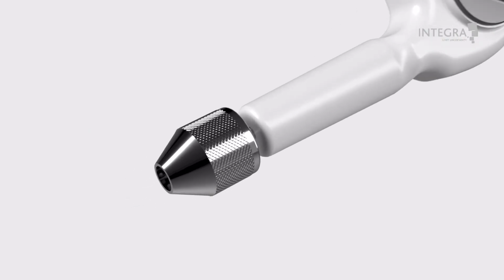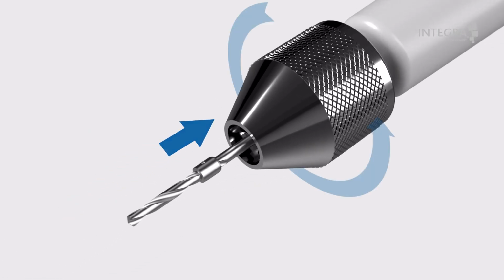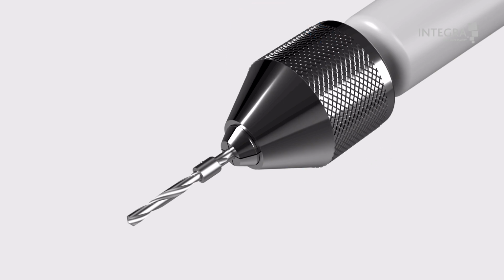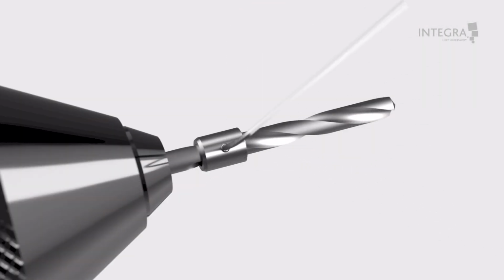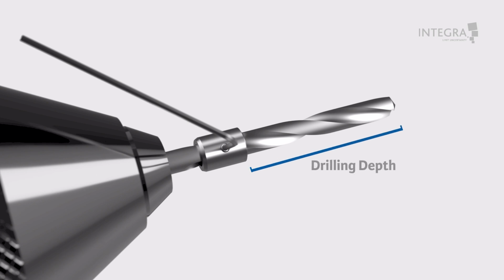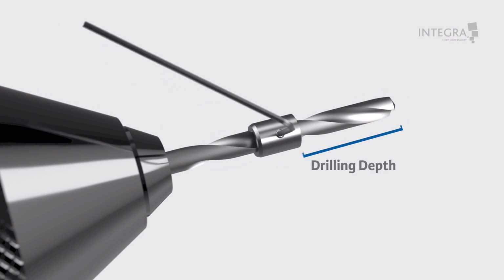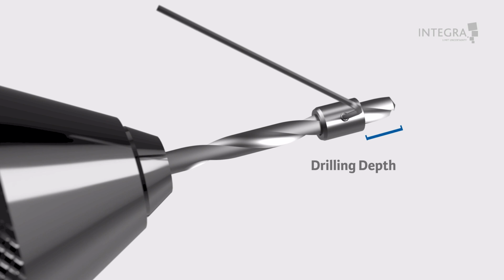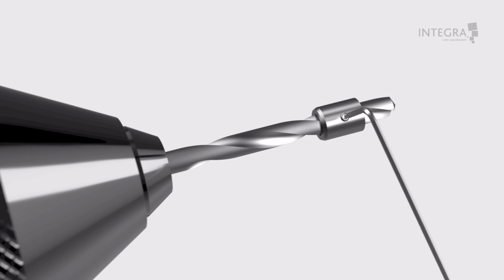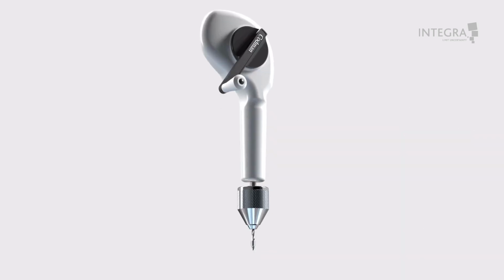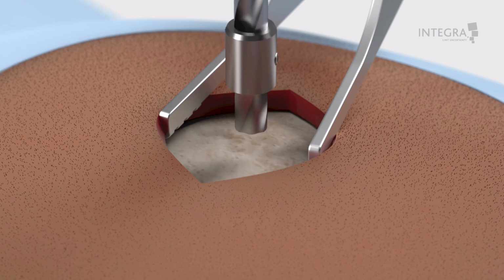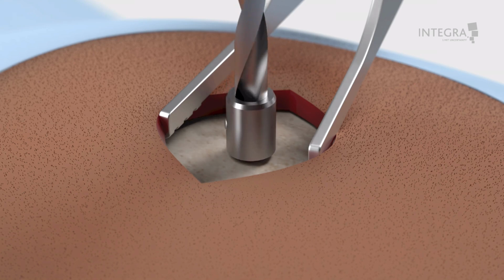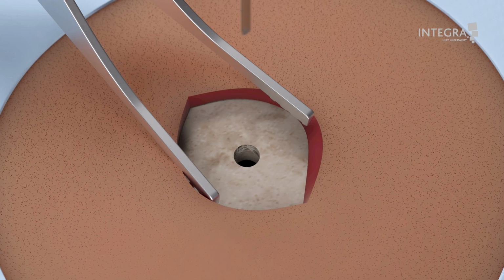Place the bit into the chuck, then hold the drill handle in place and turn the chuck counterclockwise to tighten the bit. Next, loosen the drill depth guide with the appropriate hex wrench and carefully slide the drill guide towards the tip of the bit until the desired skull depth is reached. It is important to note that the drill guide will not stop the drill. It is designed only to provide the neurosurgeon with a marker for drilling depth. Finally, tighten the drill guide in place with a hex wrench and begin drilling. Open the dura with an appropriate needle or blade.